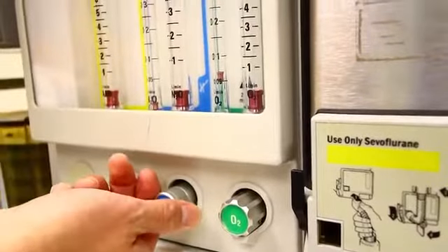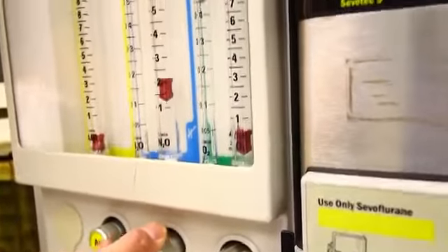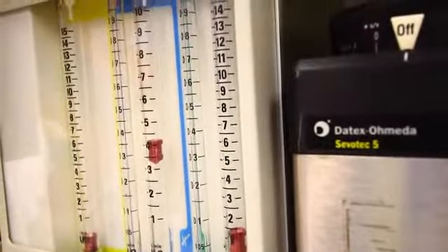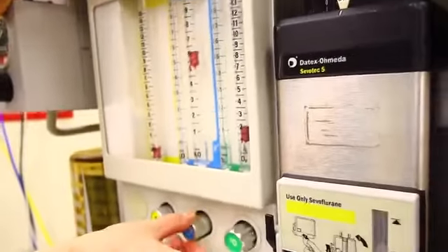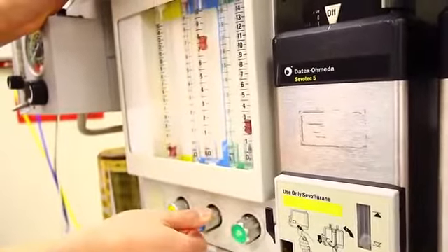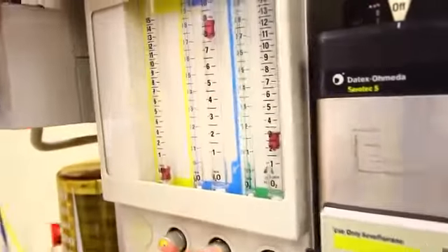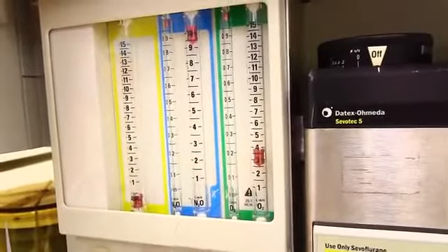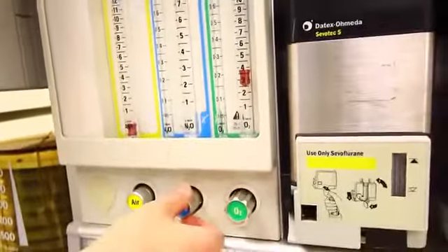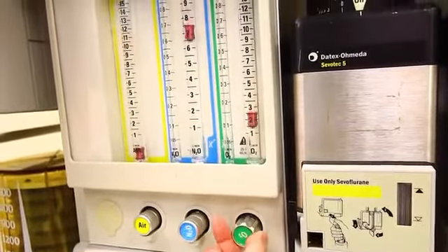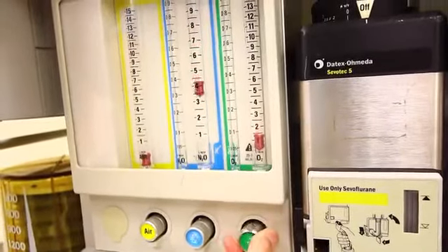Attempt to create a hypoxic oxygen to nitrous mixture and verify correct changes in flow and/or alarm. Notice the nitrous knob turns automatically as the oxygen flow is decreased.